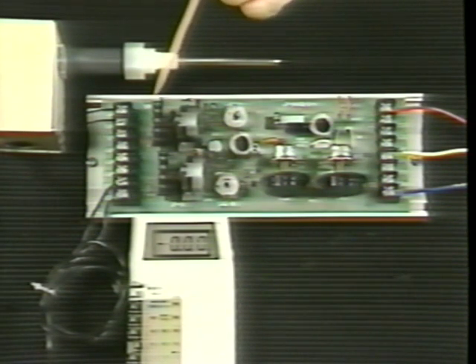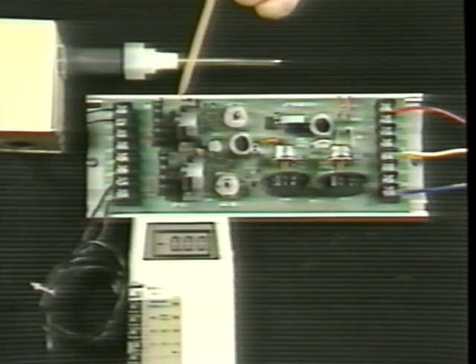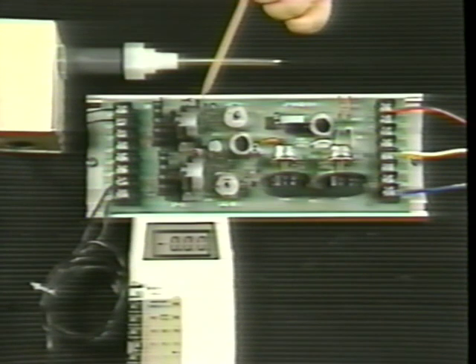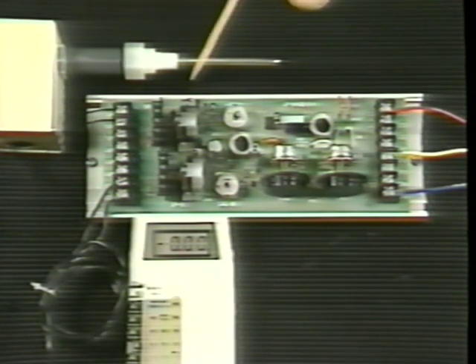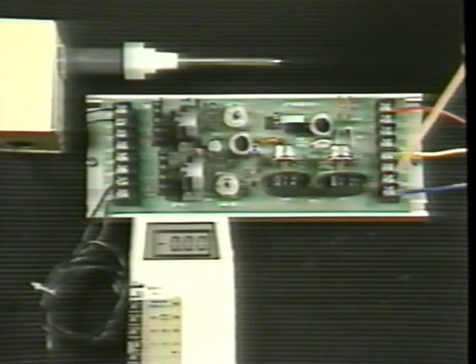If a remote set point adjuster is being used, set point A should have been disabled and the adjustment is made at the remote set point adjuster. Measure the output signal across OP1 and common with a standard voltmeter.